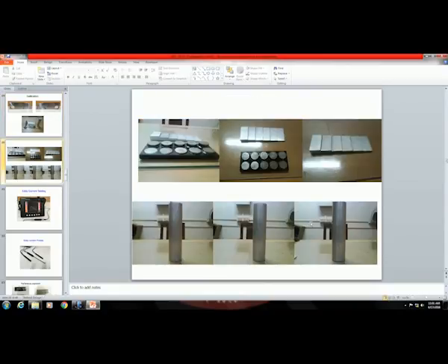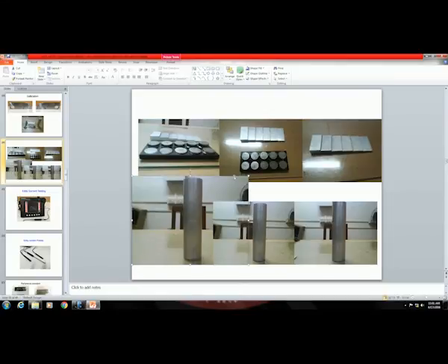Okay, so, these are the different types of calibration block, as you could see. For example, you could use a cylinder like this, and if you take a close look, let me magnify this, let me increase the size. Okay. So, I do not know whether on the screen you could see around this area there is a small hole.